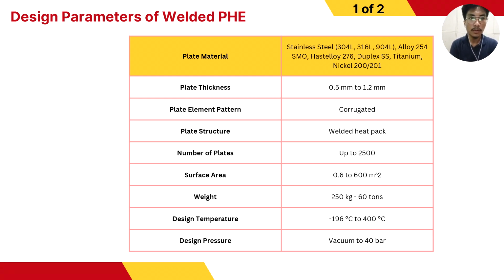And with lower temperature, less than 1.2 millimeters or above 0.5 millimeters is going to be utilized. And when it comes to fluids that have water, soda, and oil contents, 0.5 millimeters is normally used. However, with acids, strong alkalis, and corrosive mediums, 0.6 to 0.7 millimeters is acceptable. So those are the factors where the plate thickness varies.